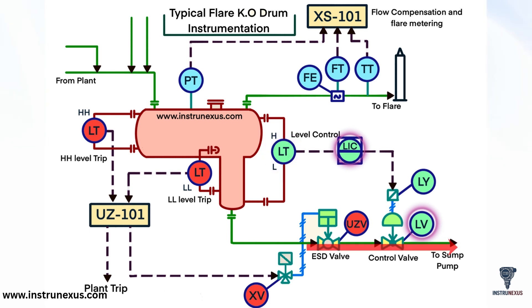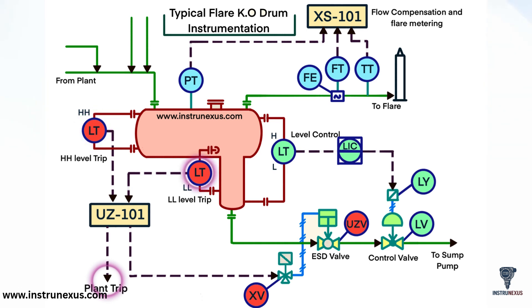Two additional level transmitters provide safety trips. The high-high level trips the plant upstream and isolates — closing the emergency shutdown valve (UZV) — in the inlet line to prevent liquid carryover into the flare header. The low-low level trip prevents pump cavitation by closing the ESD valve in the outlet line if the vessel empties too far.